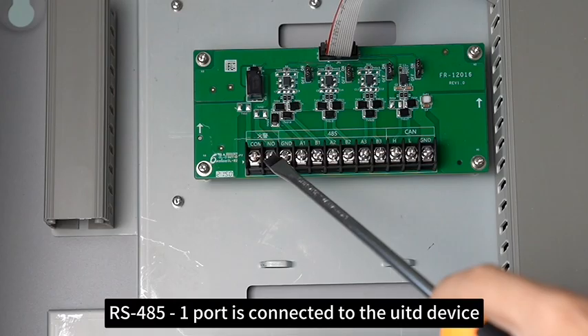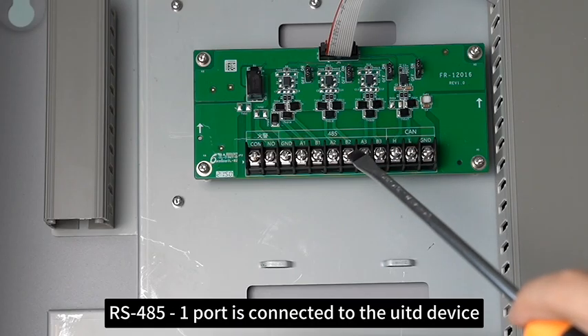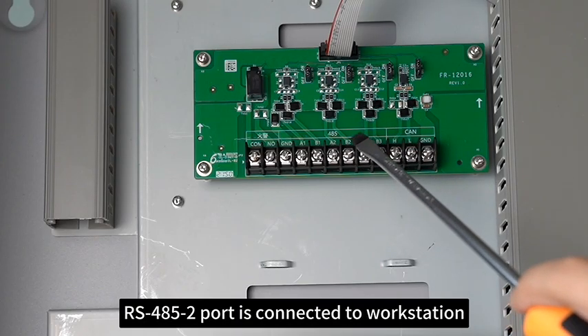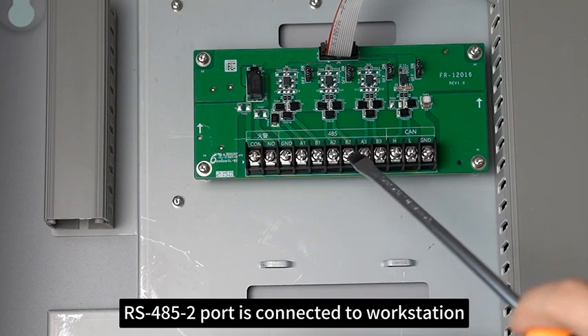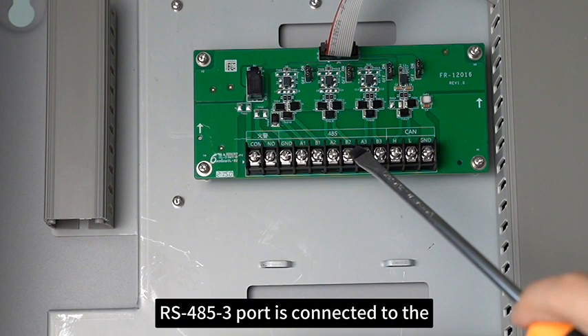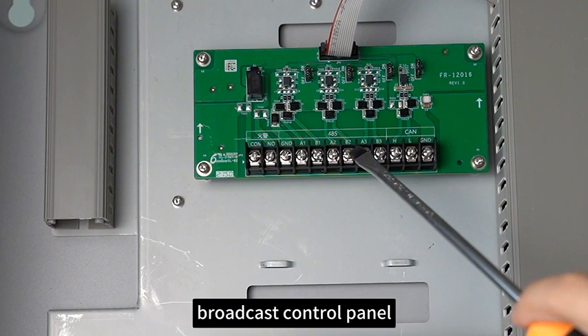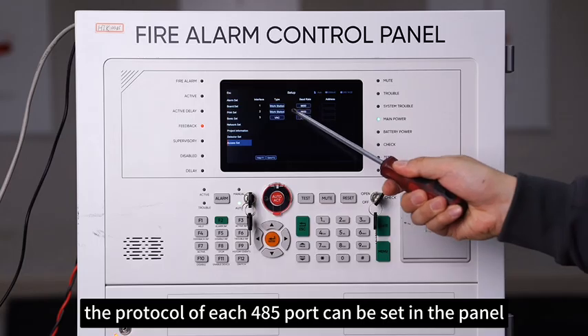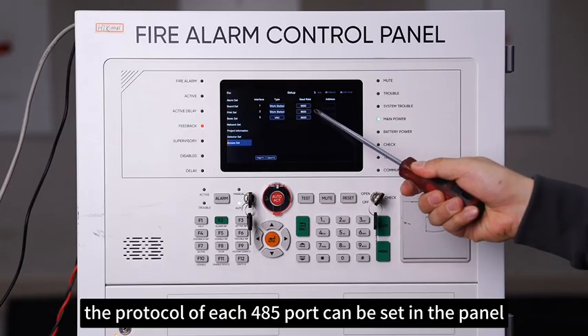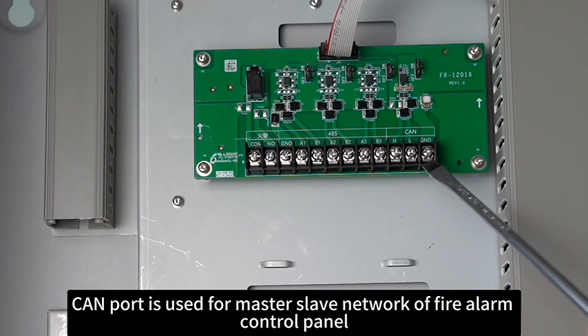RS-485-1 port is connected to the UITD device, RS-485-2 port is connected to workstation, RS-485-3 port is connected to the broadcast control panel. The protocol of each 485 port can be set in the panel menu settings. CAN port is used for master-slave network of fire alarm control panel.